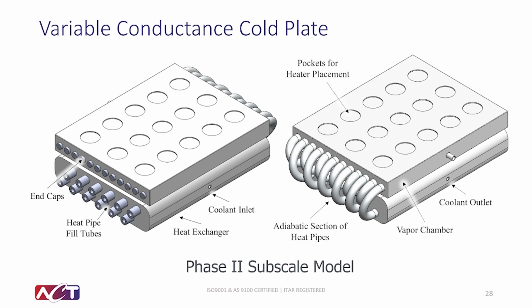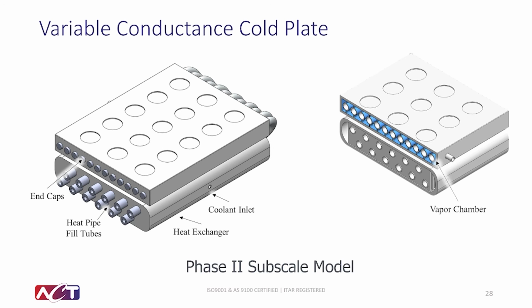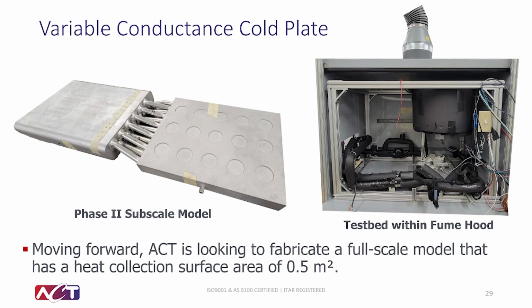Instead, we chose to fabricate the vapor chamber and the two-phase heat exchanger separately, as we'll see in the next image. I do want to note that on the interior of the vapor chamber, the heat pipes were fully embedded within the vapor space. This was done to limit the thermal resistance. And now, as you can see here, this is the fabricated Phase 2 subscale VCCP. While some work is still being done to complete the fabrication, such as we still need to charge the heat pipes, this cold plate is really just about ready for testing.